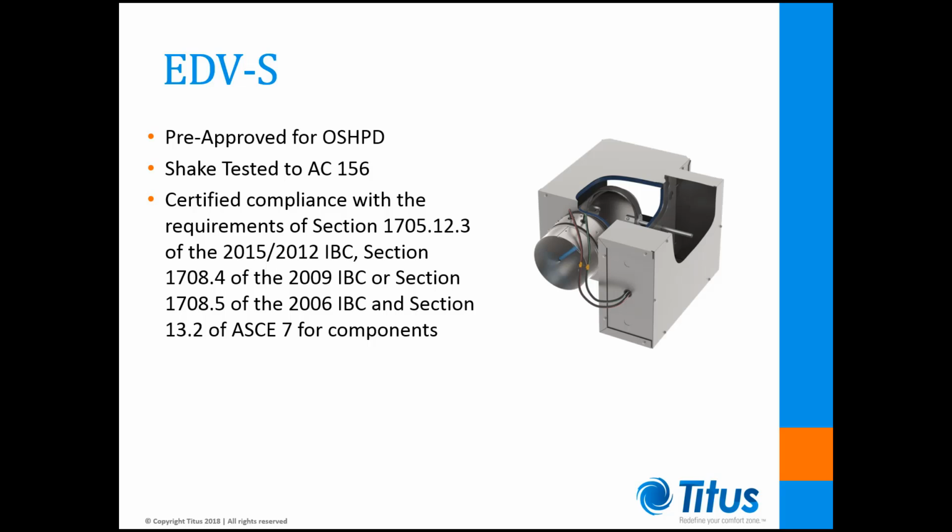For this fictional scenario, I would recommend our EDV-S, as it has already gone through rigorous shake testing per AC 156 as required by code and would fulfill the needs of this particular project.